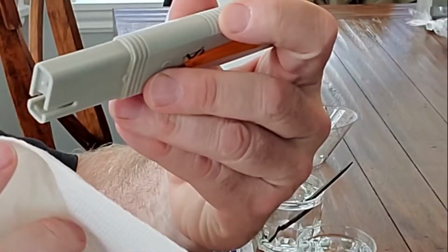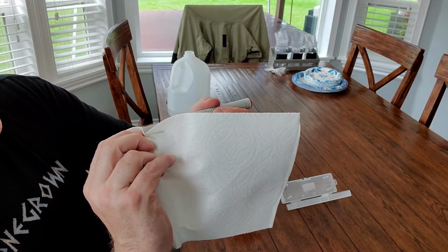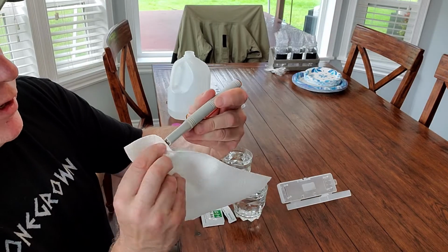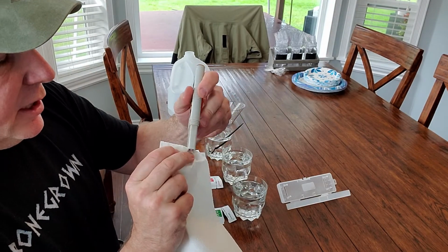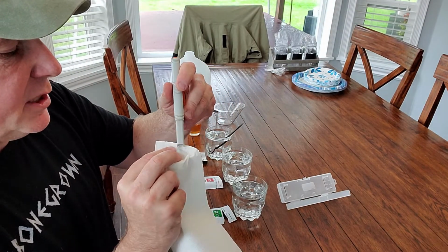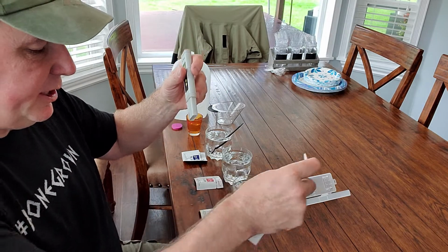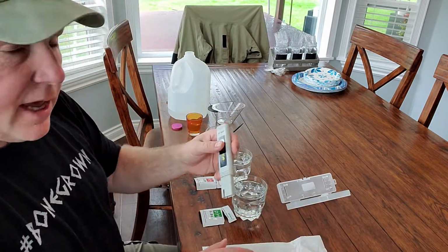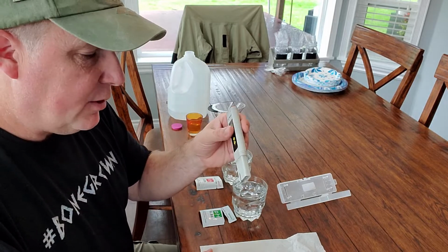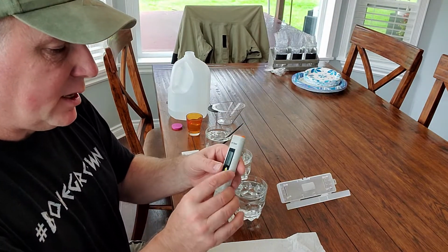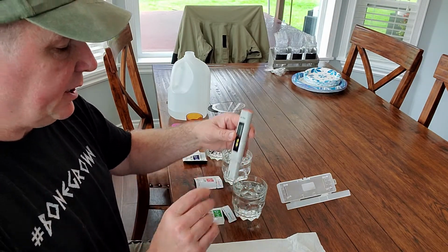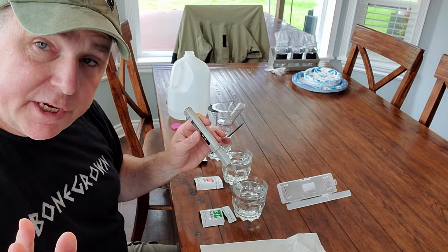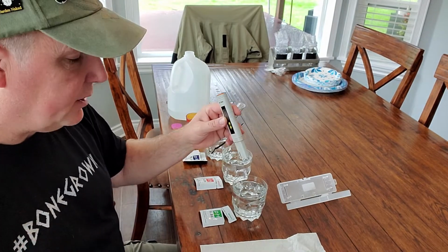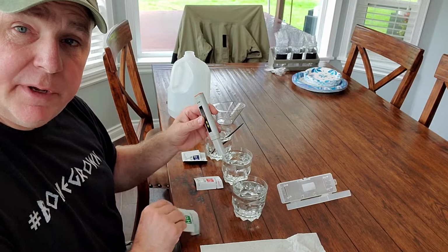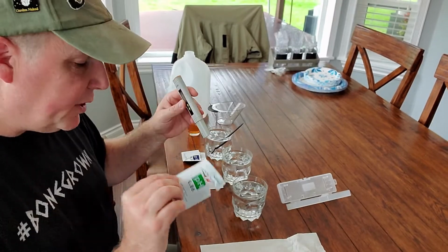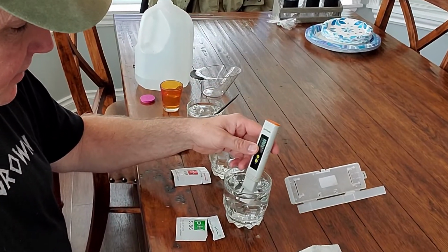You see that bulb in there, and that's what you're trying to make sure everything's clean and it's free of impurities, anything that could make the test erroneous. So I go in there and clean it. Now that I have it cleaned off and wiped down as best as I can, I'm going to go ahead and turn it on. Now, the first thing you're going to do is check the calibration. You're going to come into your 6.86 solution.